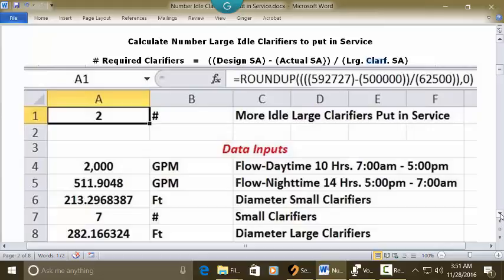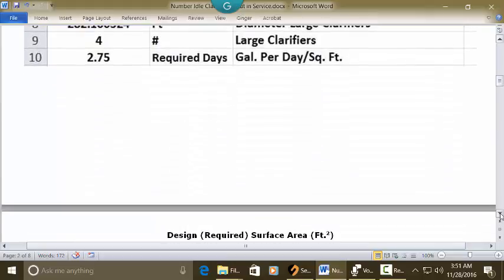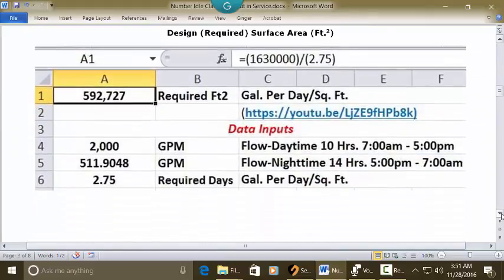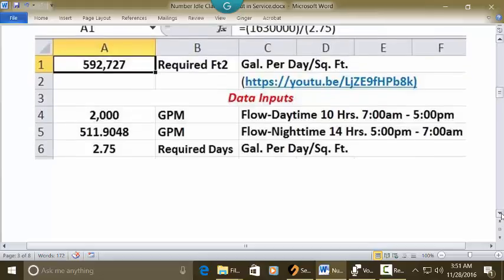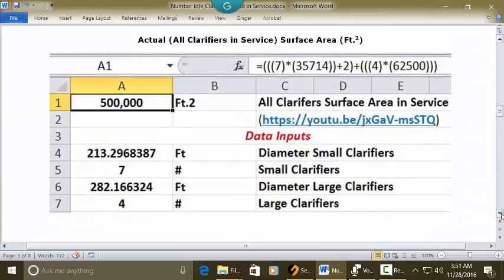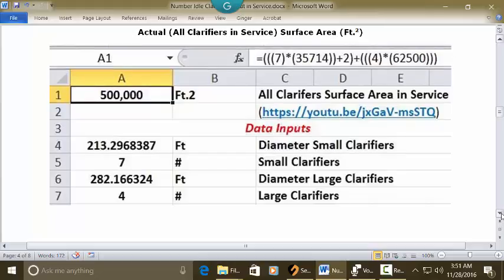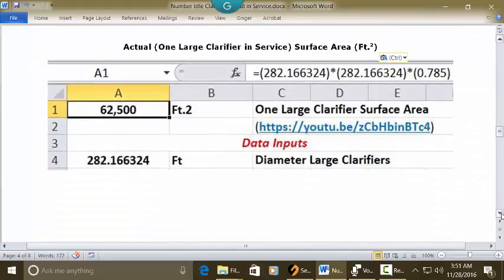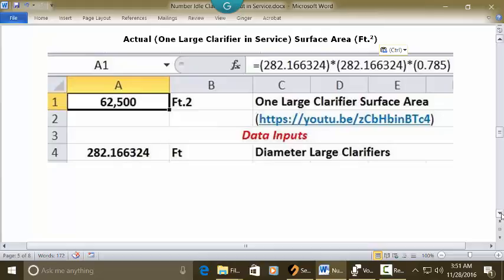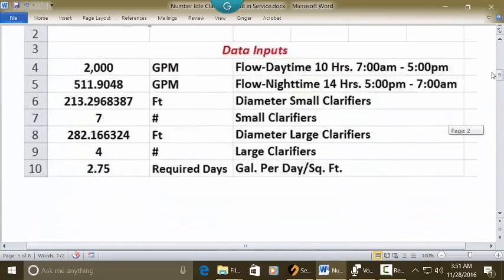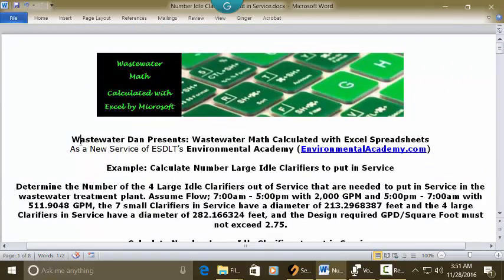How did we get to 592,727? Sliding down here, that is the design surface area — this is where we have the results and the link and formula for the 592,000. The actual surface area of the clarifiers in service gives us the 500,000, shown with the solution, the link, and the title. The surface area of one large clarifier is shown here with the formula, the result, and the link to the video: 62,500. So the answer ultimately is two idle clarifiers.